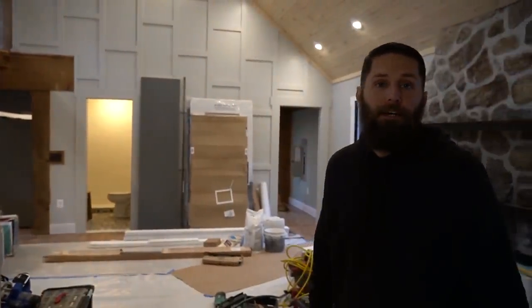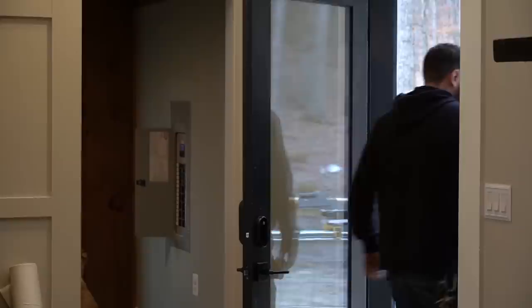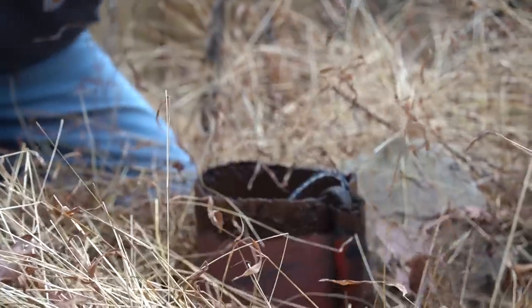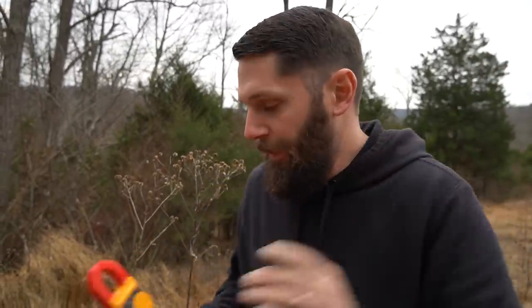We have power to the switch. He's going to go out to the well head and see what the issue is because nothing's moving. We're checking for voltage because we have power going to the switch itself — it splices right here, comes from the house, and we don't know if it's cut in between somewhere. If we don't have voltage here, it means it's cut between here and there. We're not surprised because the main service is cut in between somewhere too. So we'll have to see.